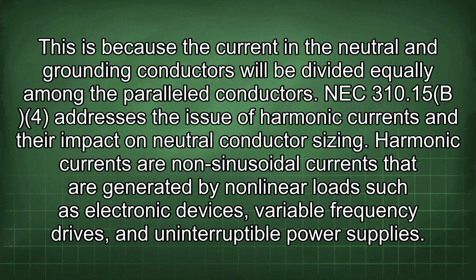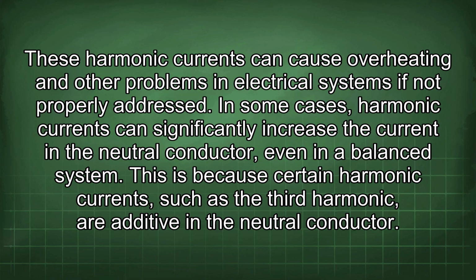NEC 310.15(B)(4) addresses the issue of harmonic currents and their impact on neutral conductor sizing. Harmonic currents are non-sinusoidal currents that are generated by nonlinear loads such as electronic devices, variable frequency drives, and uninterruptible power supplies. These harmonic currents can cause overheating and other problems in electrical systems if not properly addressed.